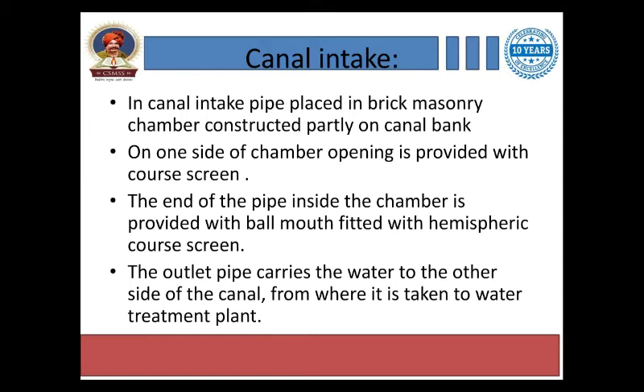In the canal intake, a pipe is placed in brick masonry chambers constructed partially on the bank. On one side of the chamber, an opening is provided with a coarse screen. The end of the pipe inside the chamber is provided with a bell mouth fitted with a hemispherical coarse screen. The outlet pipe carries the water to the other side of the canal, from where it is taken to the water treatment plant.